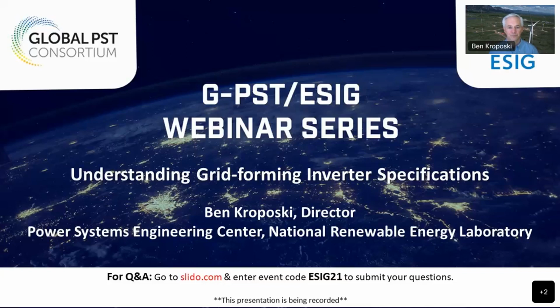Okay, this last one, I'm not quite sure exactly, but it reads, how well does the instantaneous IBR formula go with FERC's November 22 rulings on concerns over reliability gaps associated with IBRs? Instantaneous IBR formula. Well, I think the challenge with the instantaneous IBR level is it's just one point. It's convenient to have a conversation around. It surely doesn't tell you if the system is stable at that point or not. And as I showed on some of those graphs, you can be unstable at 20% inverter-based resources if you put them in the wrong places. So again, it's system dependent. But in general, in terms of rules of thumb and places we've been able to migrate the industry toward, it's this higher level, say 60 plus instantaneous with inverter-based resources. You want to start considering grid forming technologies.